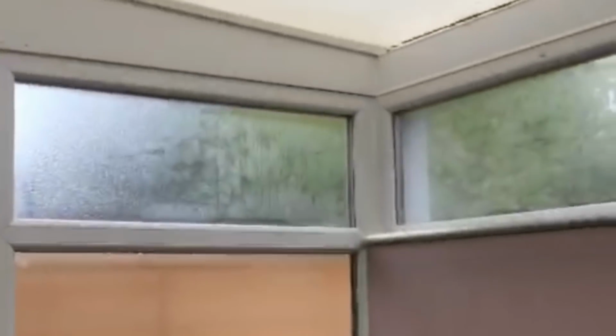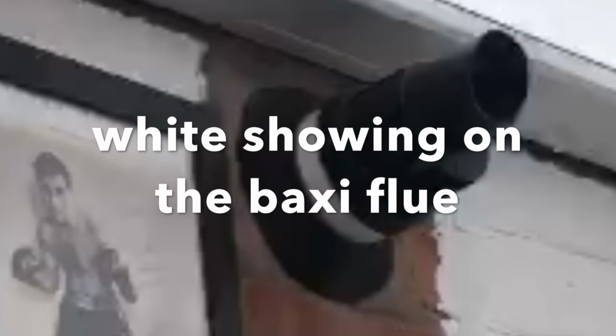Cheers. And finally, I want to finish with this flue. And this is not a joke, guys. This is actually what one of my ex-trainees found on a job. They found the back boiler was fluing into the conservatory. And basically the customers were told to keep the windows open when the boiler was running. I just can't believe anybody would be that stupid to tell them that, or that stupid to believe them. How dangerous is this?